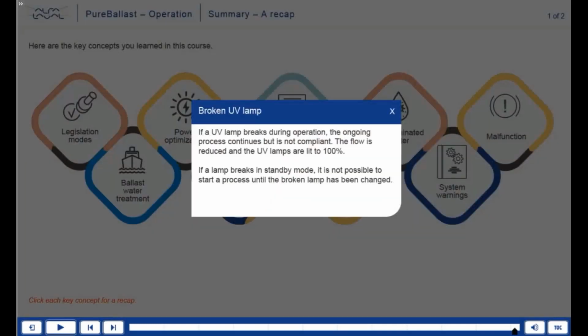If a UV lamp breaks during operation, the ongoing process continues but is not compliant. The flow is reduced and the UV lamps are lit to 100%. If a lamp breaks in standby mode, it is not possible to start a process until the broken lamp has been changed.